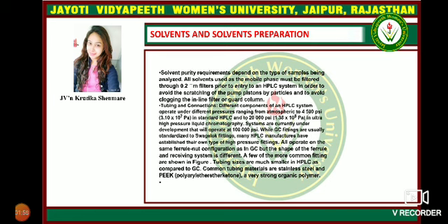The tubing and connections. Now talking about the tubing and connections, different components of the HPLC system operate under different pressures ranging from atmospheric to 4500 psi, pounds per square inch, that is 3.10 × 10^7 pascals in standard high pressure liquid chromatography, and to 20,000 psi, that is 1.3 × 10^8 pascals in ultra high pressure liquid chromatography.